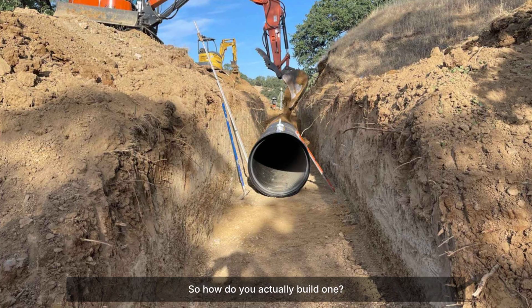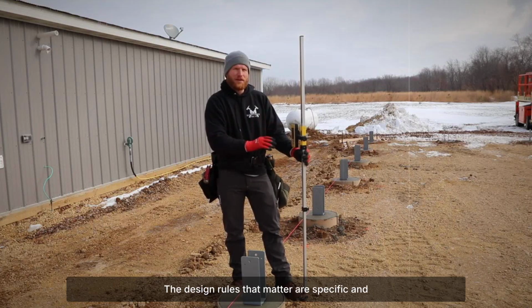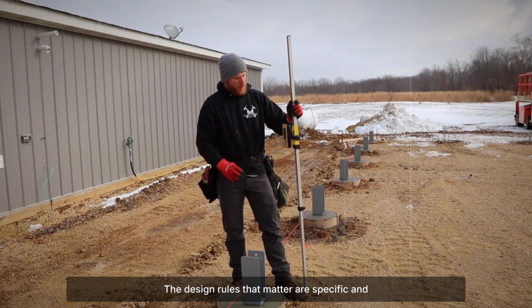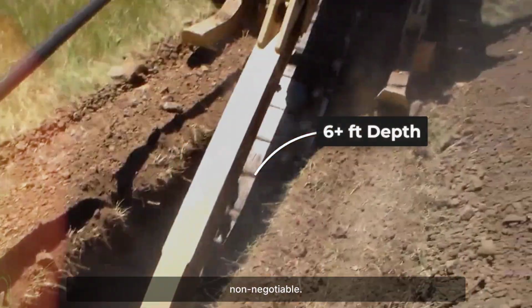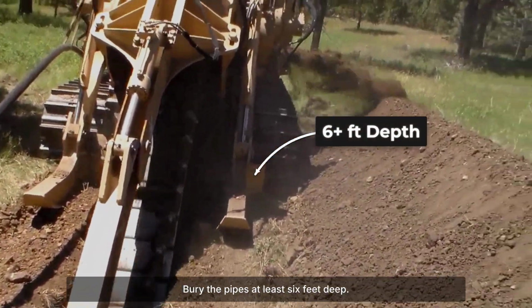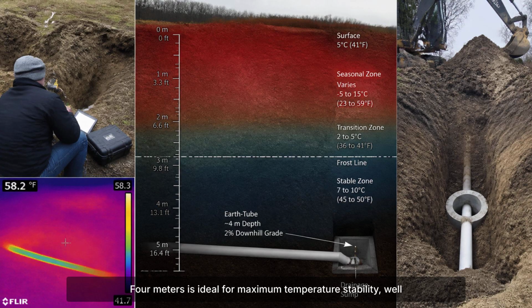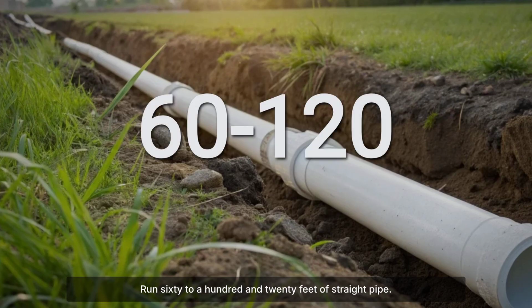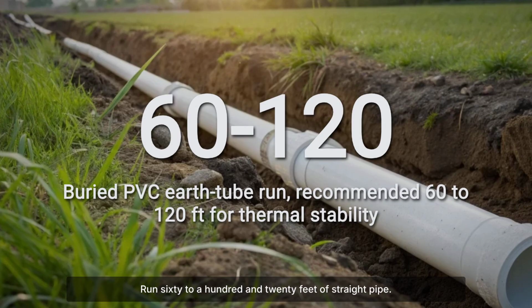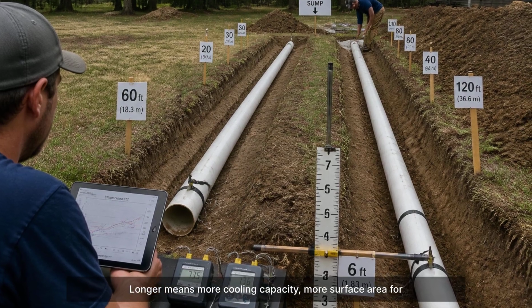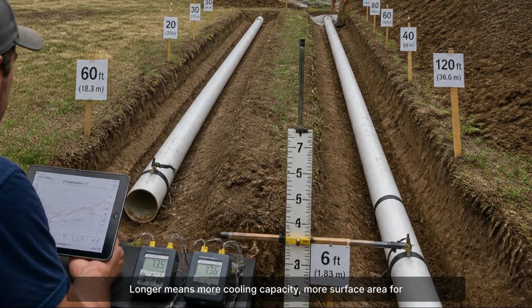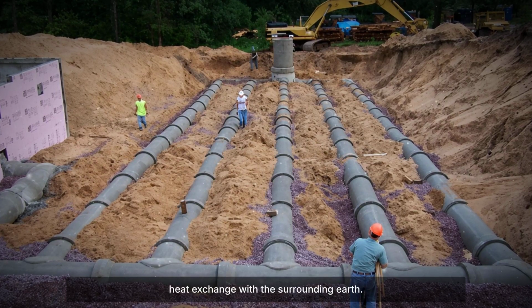So how do you actually build one? The design rules that matter are specific and non-negotiable. Bury the pipes at least 6 feet deep. 4 meters is ideal for maximum temperature stability, well below the frost line where seasonal temperature swings cannot reach. Run 60 to 120 feet of straight pipe. Longer means more cooling capacity, more surface area for heat exchange with the surrounding earth.